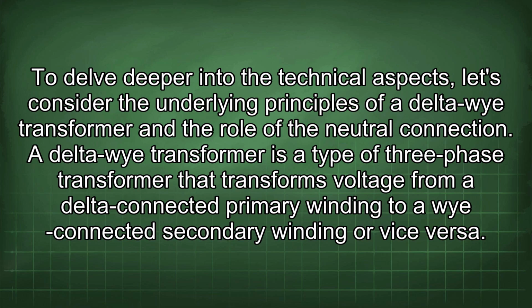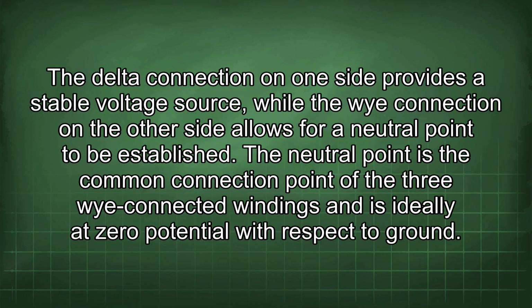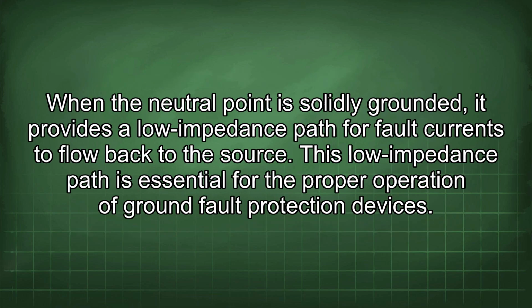A delta-wye transformer is a type of three-phase transformer that transforms voltage from a delta-connected primary winding to a Y-connected secondary winding, or vice versa. The delta connection on one side provides a stable voltage source, while the Y connection on the other side allows for a neutral point to be established. The neutral point is the common connection point of the three Y-connected windings and is ideally at zero potential with respect to ground. When the neutral point is solidly grounded, it provides a low impedance path for fault currents to flow back to the source. This low impedance path is essential for the proper operation of ground fault protection devices.